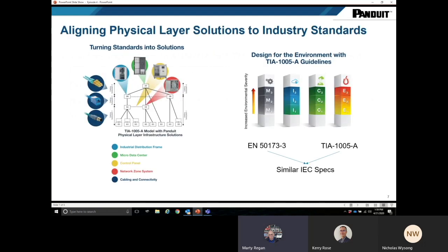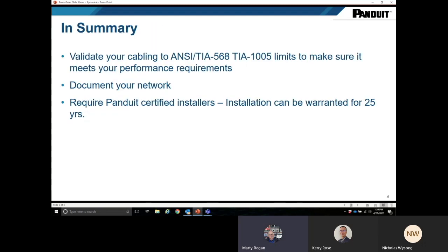Validation per the ANSI TIA 568, TIA 1005 limits will ensure performance requirements are met. Proper documentation is a key aspect of network management. Provided the installation is completed by a Panduit certified installer, the permanent cabling can be warranted for up to 25 years.